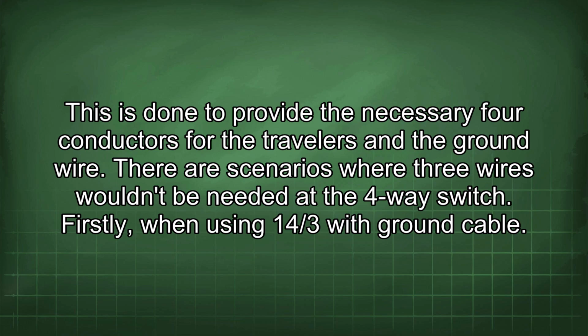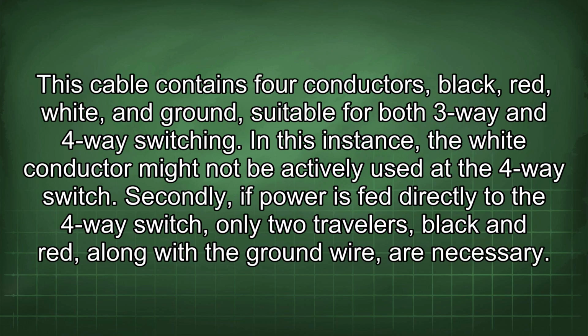There are scenarios where 3 wires wouldn't be needed at the 4-way switch. Firstly, when using 14/3 with ground cable. This cable contains 4 conductors, black, red, white, and ground, suitable for both 3-way and 4-way switching. In this instance, the white conductor might not be actively used at the 4-way switch.